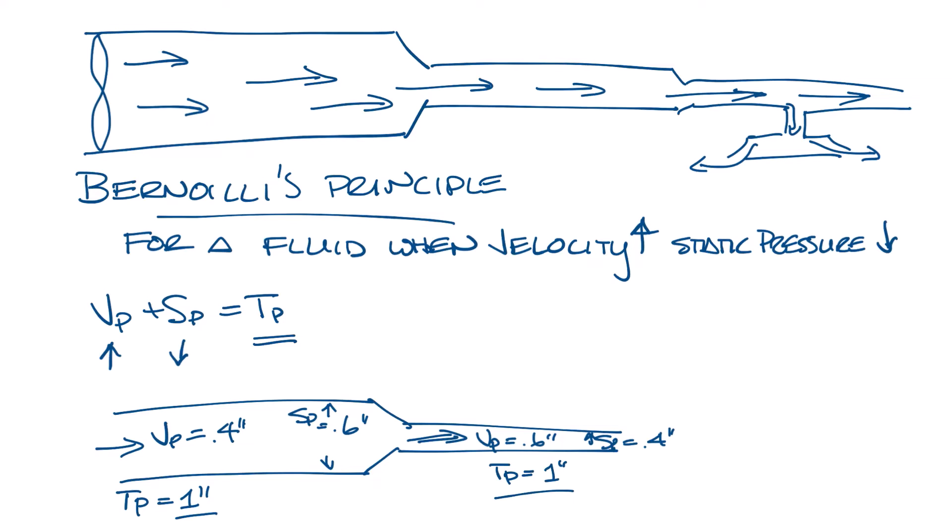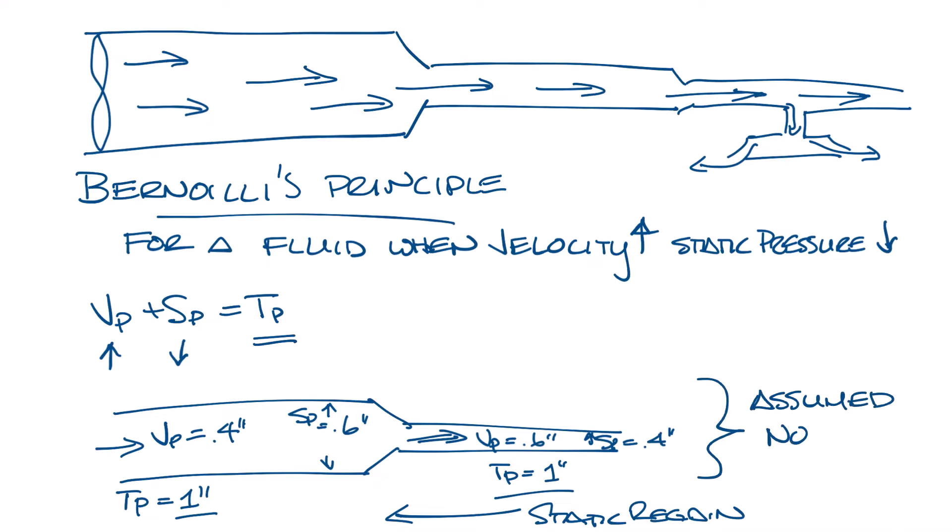Or if the airflow is moving in the other direction, then you increase the size of the ductwork. Now your velocity slows down, so your velocity pressure goes down, and your static pressure goes up. And this is called static regain. Again, I assume no friction in this example, but obviously that's not how it works in real life, so let's make some room and look at this.